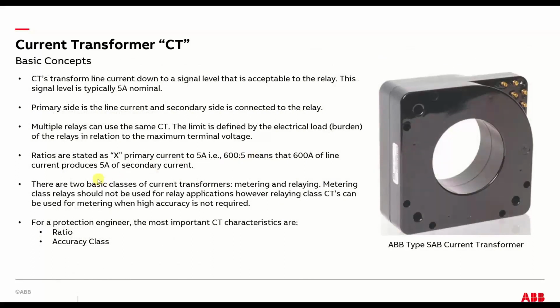I know that was a little bit contrived, but I'll see if I can clean it up a little bit. Back to the ratio, the first part of the ratio, for example, the 600 here, means that 600 amps of line current will produce a 5 amp secondary current in the CT.